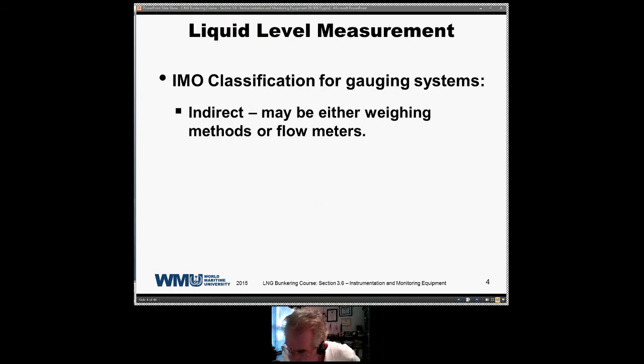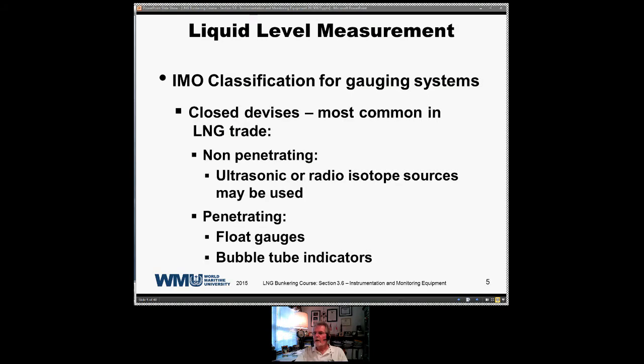IMO classifies gauging systems. There's two types, which are called indirect, and this is something we don't see in the LNG trade. It may either be weighing methods or flow meters. And then we have what are called closed devices, and these are the most common in the LNG trade. They're non-penetrating. In other words, they don't penetrate the tank itself, or there is a penetration, but it's within a closed system inside the tank. The ultrasonic and radioisotope sources may be used for the non-penetrating, and then you have penetrating types, which are the float gauges and bubble tube indicators.